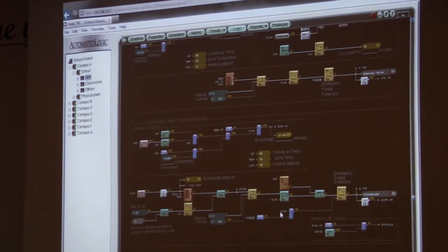Okay? This is the one nice thing about the logic page. The logic page is live. You're looking at the actual program running live. You saw me just click on my graphic, and it opened up a microblock. So now you guys know the graphic comes directly from the logic page, right? You saw me click the properties button and go looking for a schedule, and it opened a microblock. Comes from the logic page. Everything, your trends, comes from the logic page. Everything comes from this page, all right? So right here I want to find out.